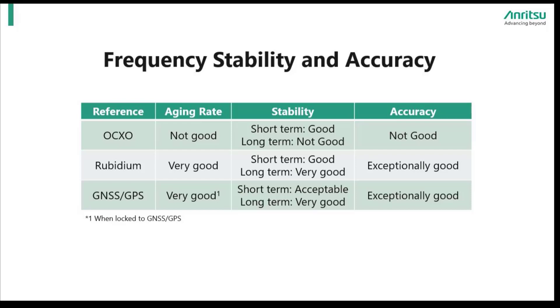We start with the OCXO, which has a poor aging rate and likewise poor long-term stability and accuracy. For some applications this performance may be enough, but for critical applications these qualities may be inappropriate.